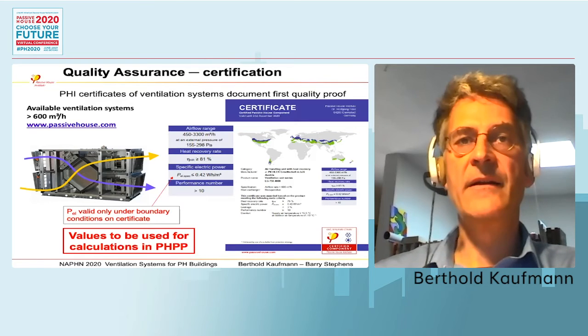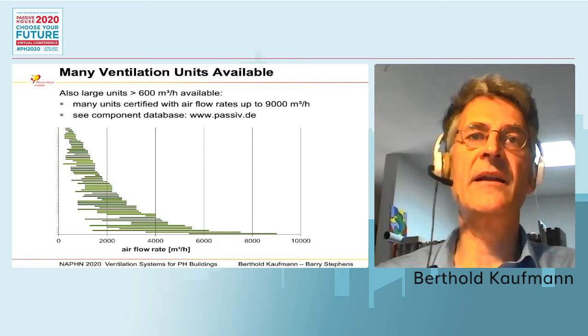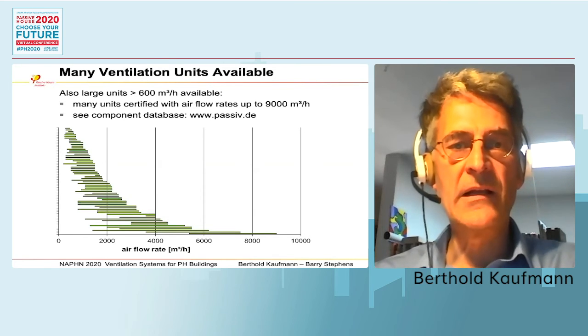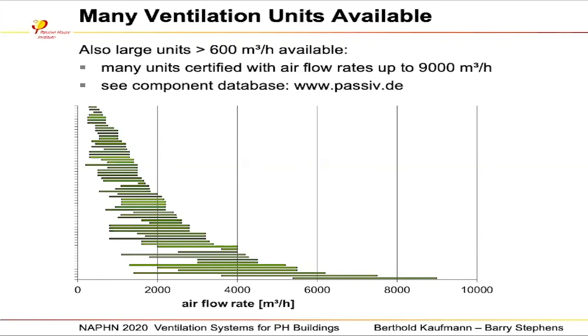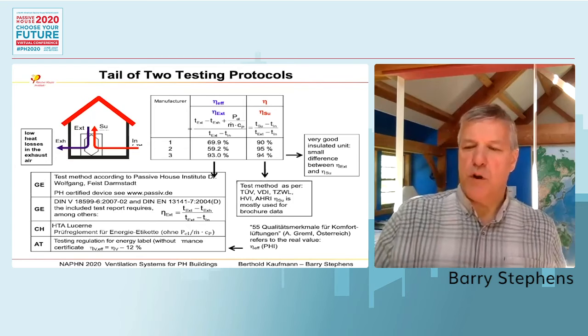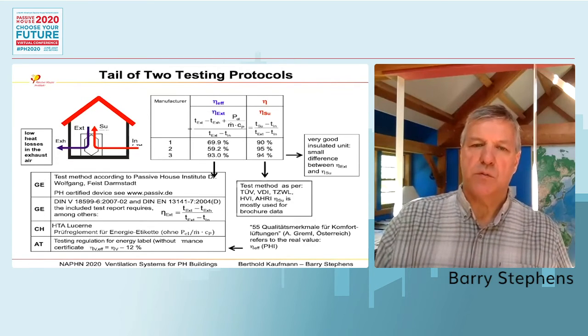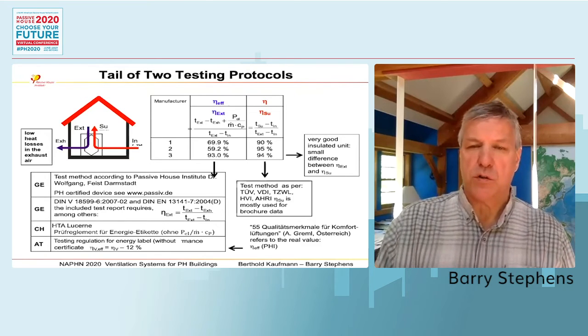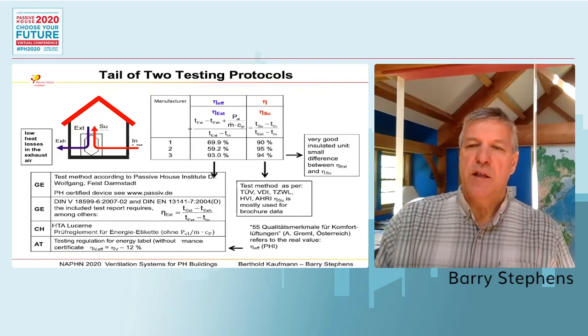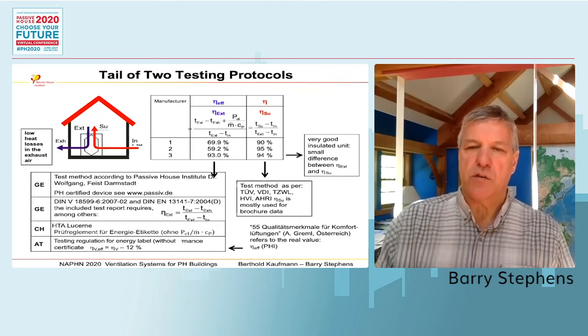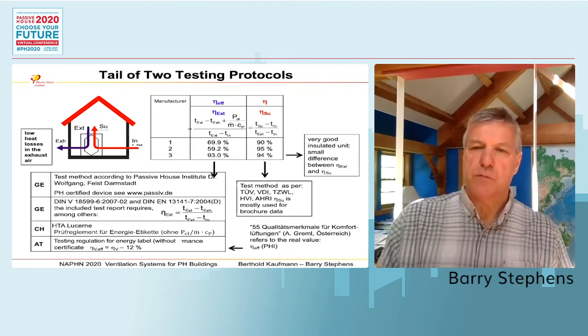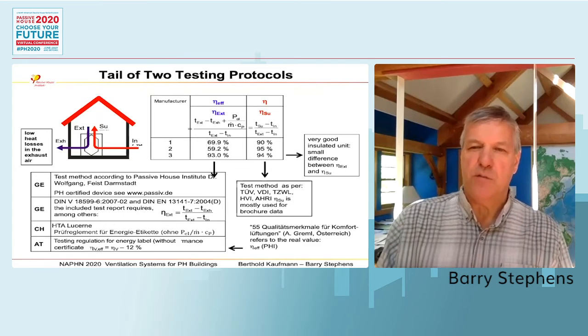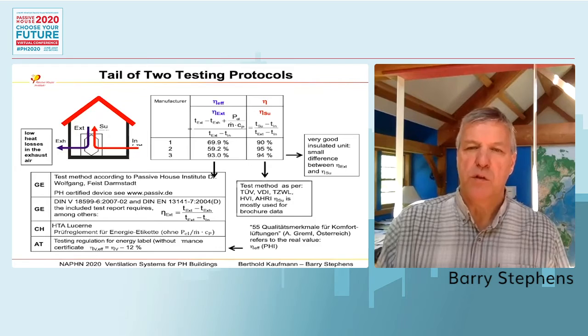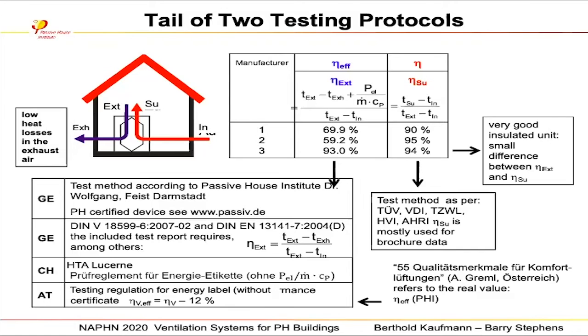On the next slide, you can see there are a variety of systems available, from smaller systems for single apartments to larger systems for office buildings and school buildings and so on. I'd like to address one of the big challenges we've had in North America: up till recently, there haven't been a lot of Passive House certified HRVs and ERVs, especially commercial ones, and we've been relying on a different testing standard. We use HVI, which is the CSA 439 testing standard for small residential HRVs and ERVs up to 300 CFM, and AHRI for larger commercial HRVs and ERVs. One of the problems is that this is a different testing standard. We've mentioned the testing standard earlier.